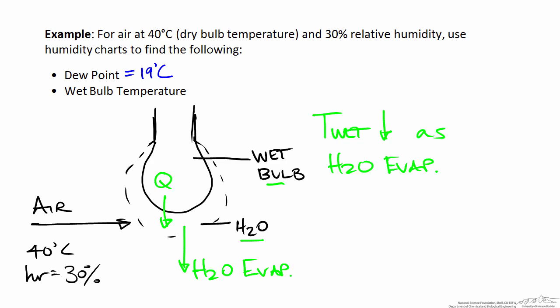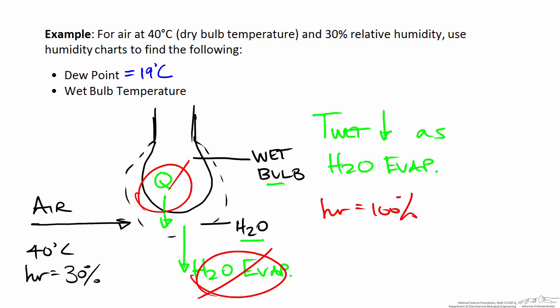The temperature of the wet bulb is driven down due to water evaporation, and how far the wet bulb temperature drops is a function of the moisture content of the air. We can think of a limiting case to illustrate this point. If the relative humidity is 100%, then air moving past the wet bulb is completely saturated with water, so water can't evaporate from the wick. If there is no evaporation, there is no heat loss, and consequently the wet bulb temperature won't change. So if the relative humidity is 100%, the wet bulb temperature equals the dry bulb temperature.